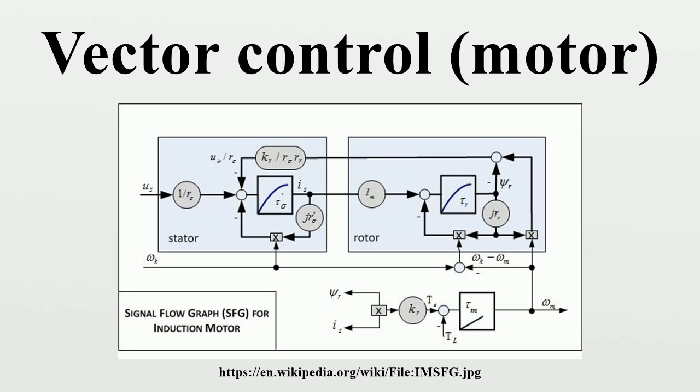corresponding current component references. Typically proportional integral controllers are used to keep the measured current components at their reference values. The pulse width modulation of the variable frequency drive defines the transistor switching according to the stator voltage references that are the output of the PI current controllers. FOC is used to control the AC synchronous and induction motors.